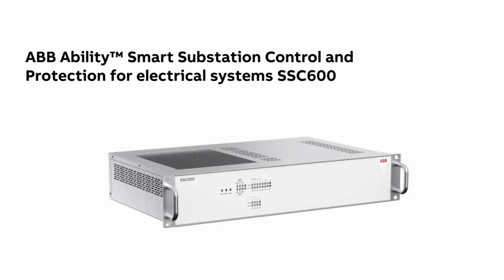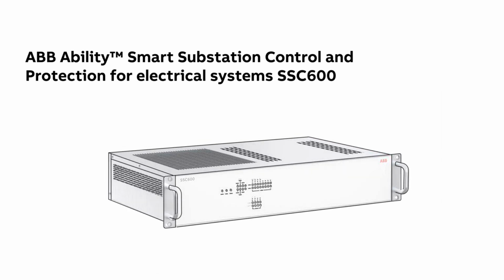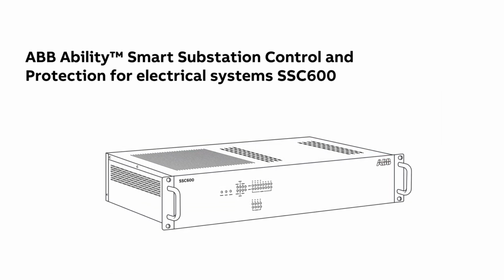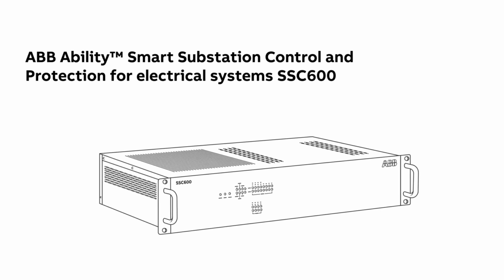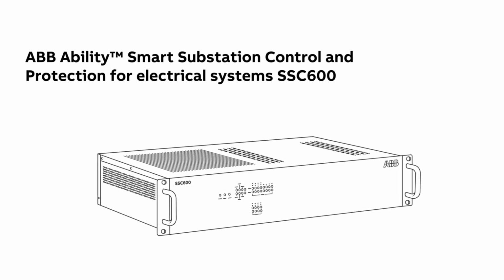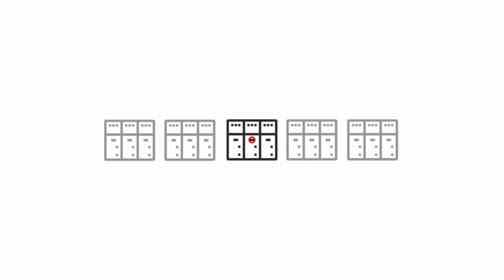ABB Smart Substation Control and Protection SSC600 covers the protection and control needs of entire substations. In addition to conventional centralized protection and control functionality, it also offers benefits specifically for arc flash protection. An arc flash is an electrical fault that results from a connection through a physical air gap or bridge between two electrodes.